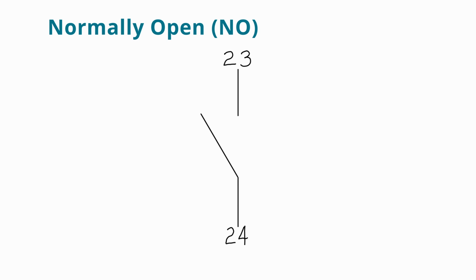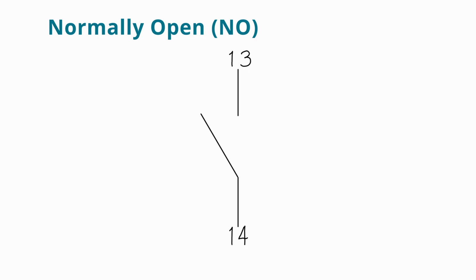Normally open contacts are open in the default state. They close when the device is activated, allowing the flow of current. They are labeled with any combination of numbers where the least significant numbers are 3 and 4. For example, they can be labeled 3 and 4, 13 and 14, 53 and 54, and so on, as long as the least significant combination of numbers is 3 and 4. The only normally open contacts which are labeled differently are the ones that you find on traditional overloads, which are labeled 97 and 98. Start push buttons which you use in a direct online starter are normally open contacts.